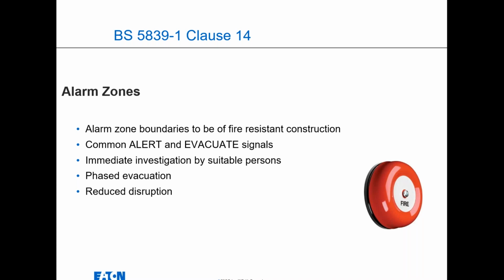Alarm zones, which we talked about, are different from detection zones. They've got boundaries that need to be fire resistant construction. And again, that needs to be understood within a design, and it's sometimes very hard to come by that information, as I know. You also have to have common alert and evac signals.